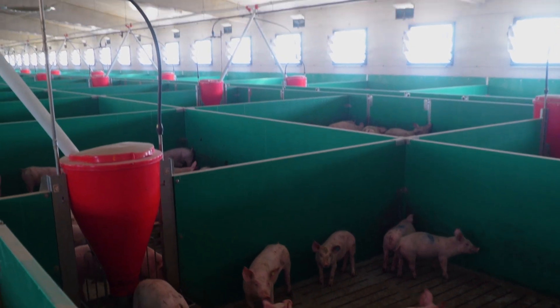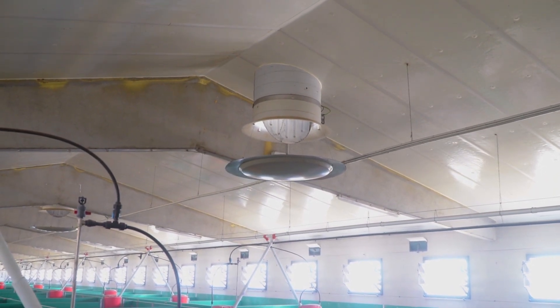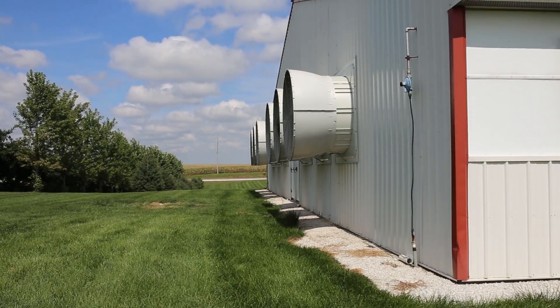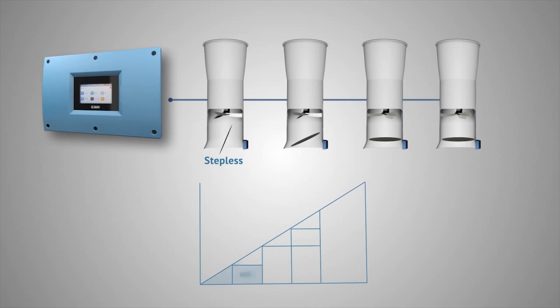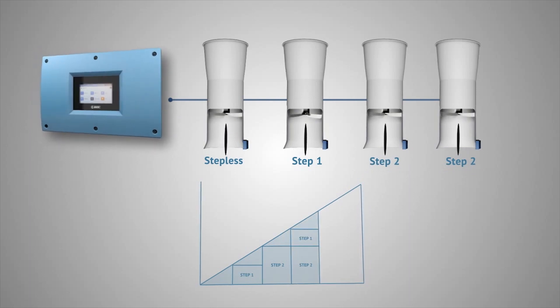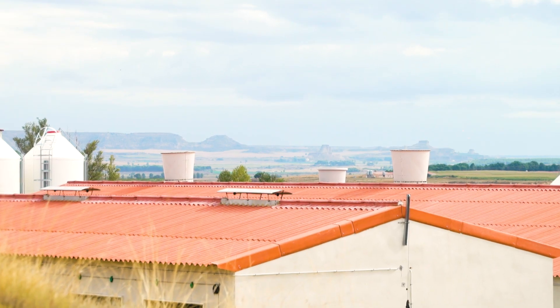It's important that the performance of air outlet units is high at a low level of energy consumption. The design of SKOV's air outlets is aerodynamic and their function is optimised in combination with fans. The air outlet is regulated according to the dynamic multi-step principle, which is unique in that the fans connect in steps until 50% of their output. When all the fans in the section have been connected up to 50%, all of them will be regulated in parallel up to 100% when additional ventilation is required.